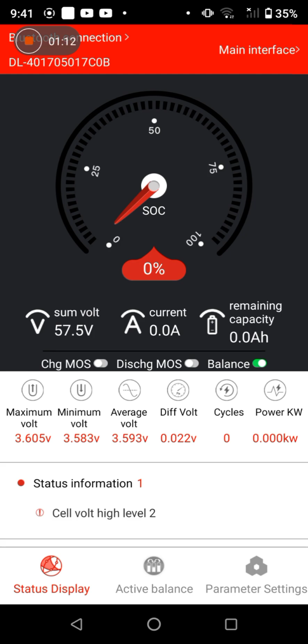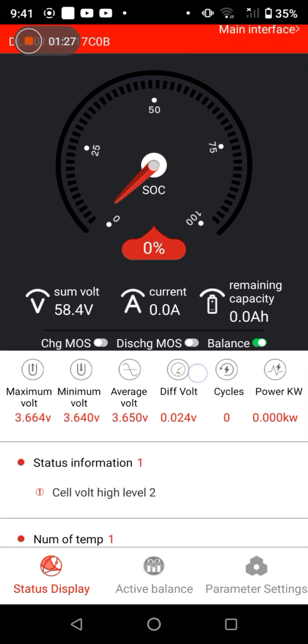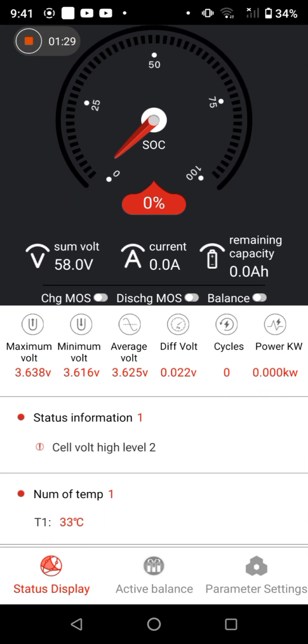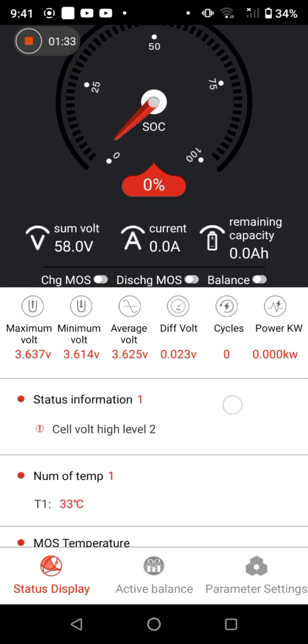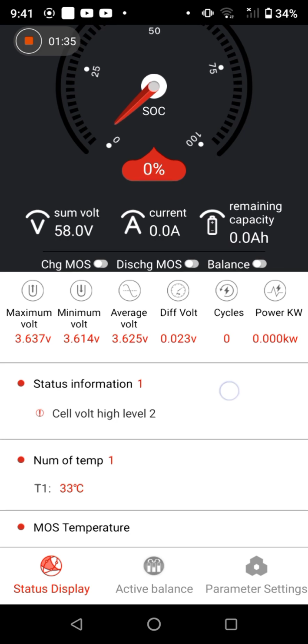One thing I have noticed is that the voltage on this is under-reading. You can see there it's at 57. Well, it's now changed to 58.4, so now it's over-reading. So the overall pack voltage reading is a bit unstable.